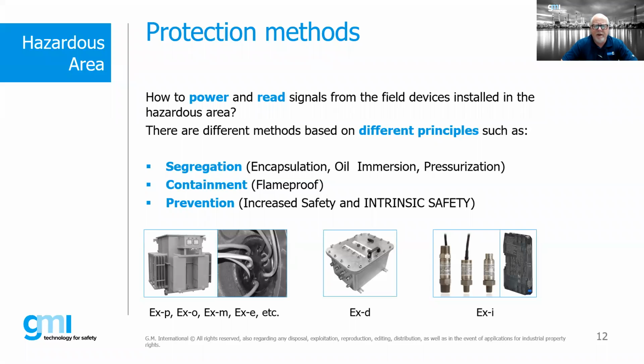And then there's also prevention, which both increased safety and intrinsic safety fall within. Increased safety basically says that as long as we meet certain creepage and clearance requirements and can eliminate the potential for an arc or spark, then that's one protection concept. With intrinsic safety, we assume we're going to have an arc or spark, but we keep it at such a low level that it's below the minimum ignition energy curve of the flammable gas-air mixture. That's the concept of intrinsic safety. All of these protection concepts are widely used, and there are pros and cons to the various protection concepts, but we'll really focus our attention on intrinsic safety.